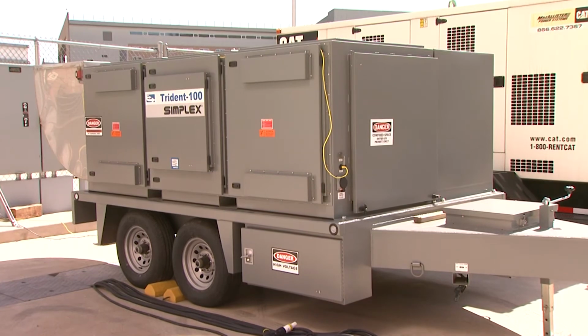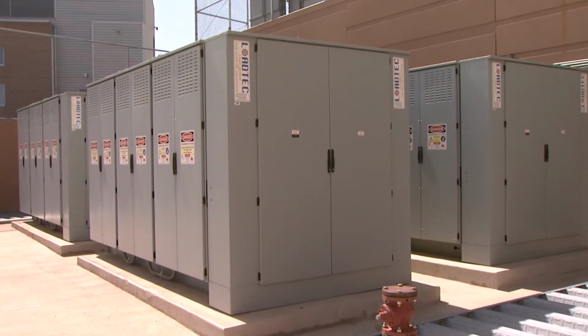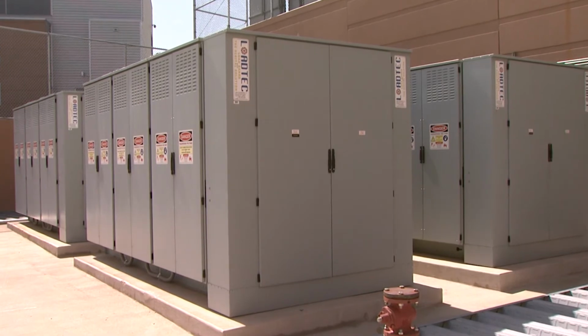First, I'd like to show you our outdoor test area. Indoors, we have several small portable load banks, but outdoors we have our 100 kilowatt and 4 250 kilowatt load banks that can replay resistive, inductive, and capacitive loads. This means I can measure real-world facilities and replay those loads here in the lab for microgrid testing.